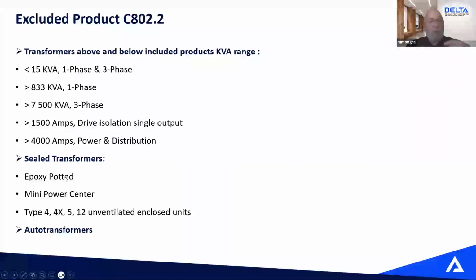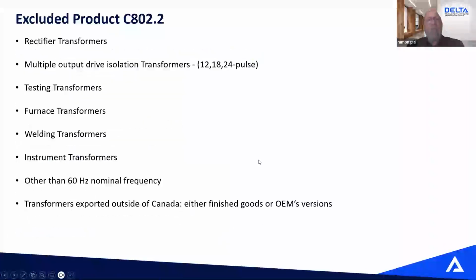Any sealed transformers, so epoxy potted, mini power center, fully enclosed like NEMA 4, 4X, NEMA 5, NEMA 12, this is all excluded from the standard. Autotransformers are excluded from the standard. And all what we call specialty transformers: rectifier duty, multi-pulse units, testing transformer, welding transformer, something that doesn't have a 60 hertz frequency. If you build something 50 hertz or 50/60 hertz, excluded. Anything that is dedicated to be exported outside of Canada doesn't have to meet NRCan, and usually the customer who buys that transformer has a 6 months period to export it outside of the country.